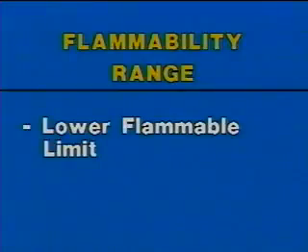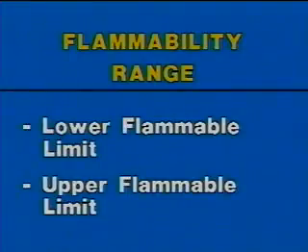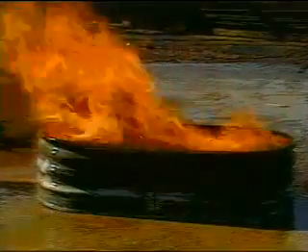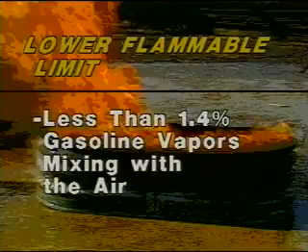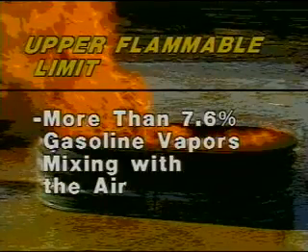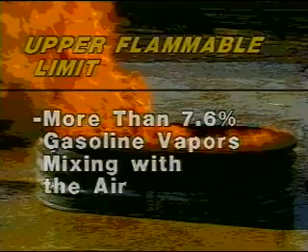Besides flash point, another important term to be familiar with is flammability range, often assigned to combustible and flammable liquids. Flammability range is a specific range of vapor-air mixture which will ignite, usually listed as the lower flammable limit and the upper flammable limit. Anywhere between these limits, ignition can occur.